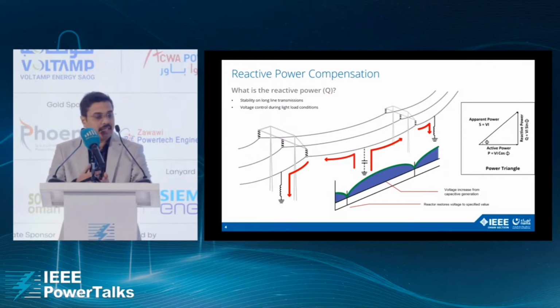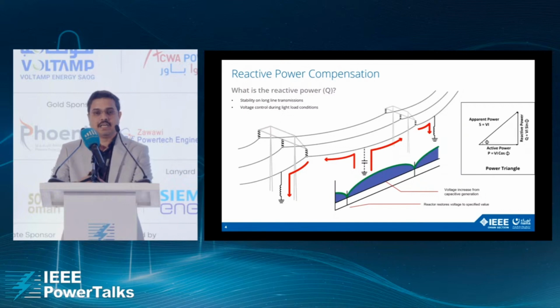And here we have shown the diagram of a very long transmission line. The transmission line has interaction with the ground, and with this interaction, it forms a virtual capacitor bank. This capacitor bank is indirectly inducing reactive power in the system. And this reactive power is increasing the voltage with the help of the Ferranti effect, which we all know. On the contrary, we have inductive loads like shunt reactors, which will consume the reactive power and bring the voltage level back to normalcy.